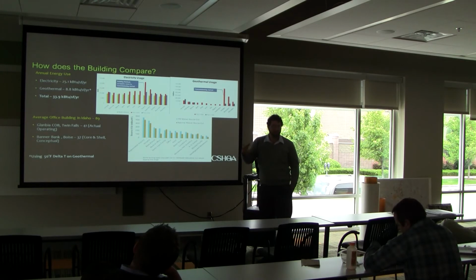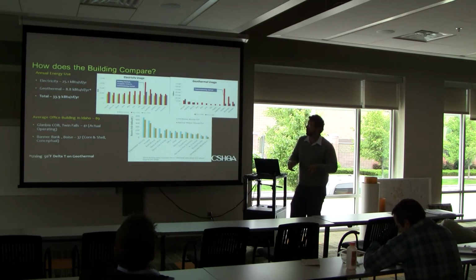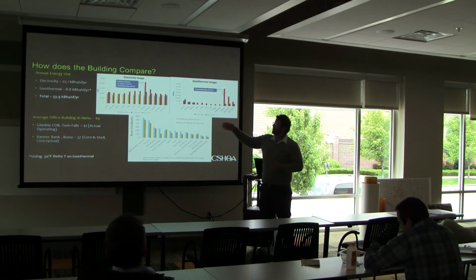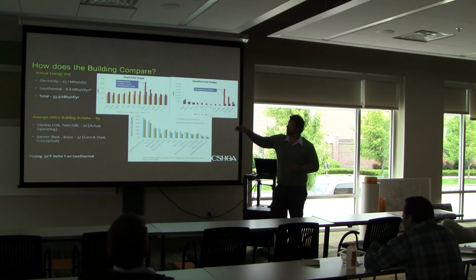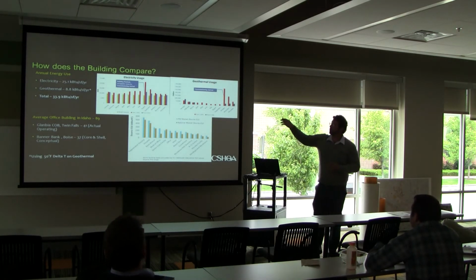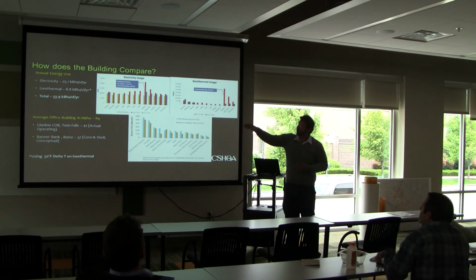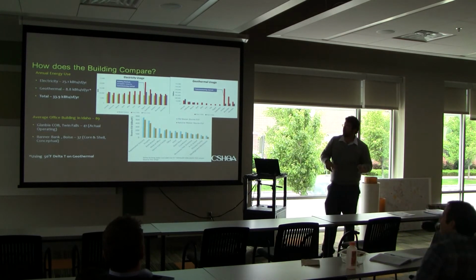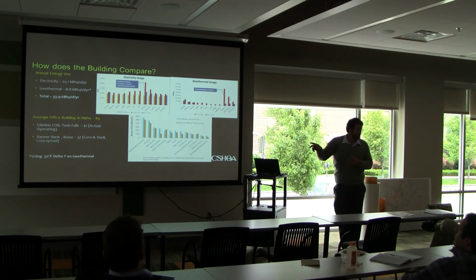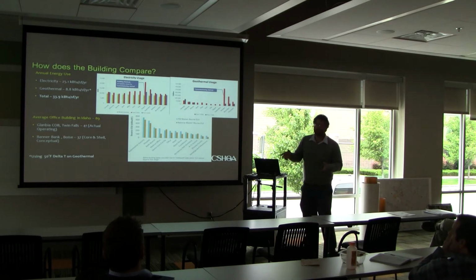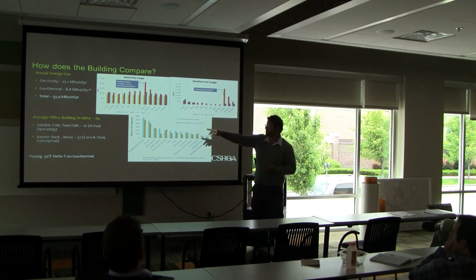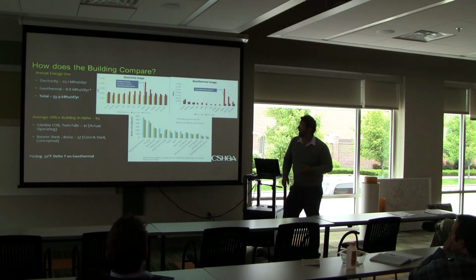It's a metric used to compare a building, an energy density per square foot. On the electricity side, we were bottoming out at about 25.1 kilo-BTUs per square foot per year. On the geothermal side, using the 50 degree delta, we're at 8.8 on the EUI side. It's incredibly low, especially compared to the average office building in Idaho, which is 89.